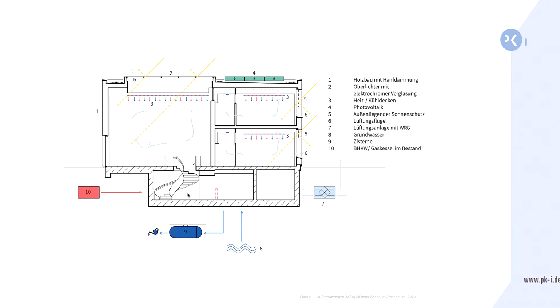Heat and cold are provided by heating and cooling ceilings. This system has the intention of providing heat and cold from above. You may wonder whether this is really doable, but it is doable if the building envelope is excellent, and since opaque and transparent components of the building envelope are very well balanced, you don't need all that much energy, so a heating and cooling ceiling is indeed suitable to supply heat in a controllable way.